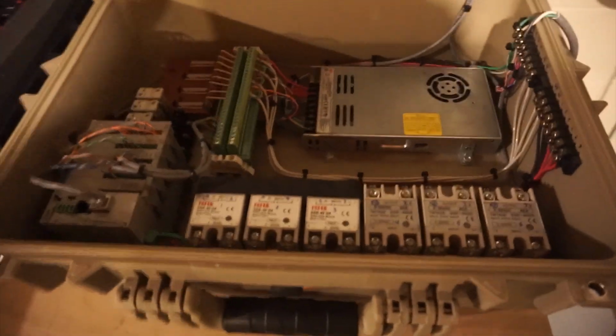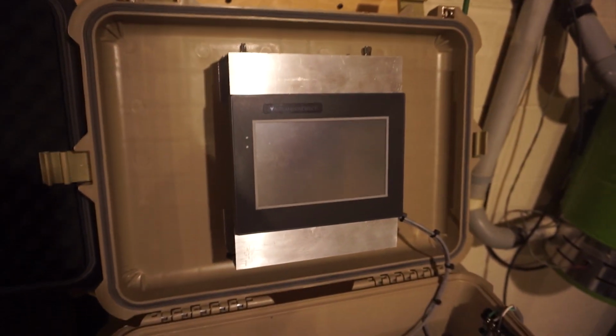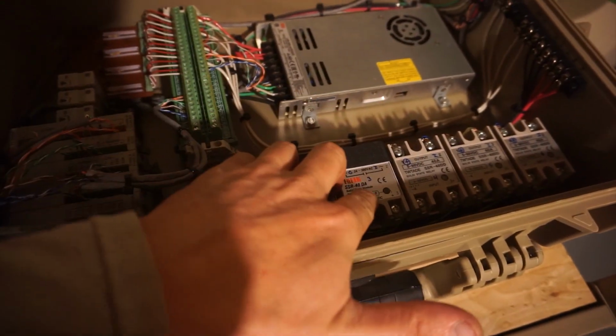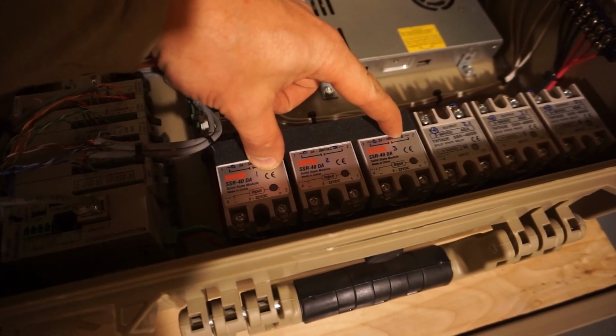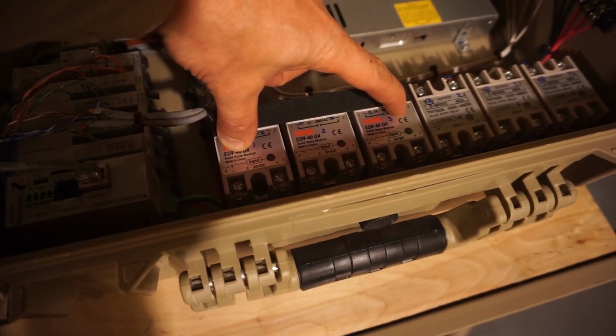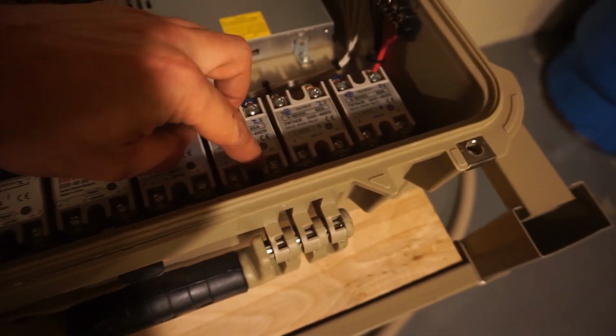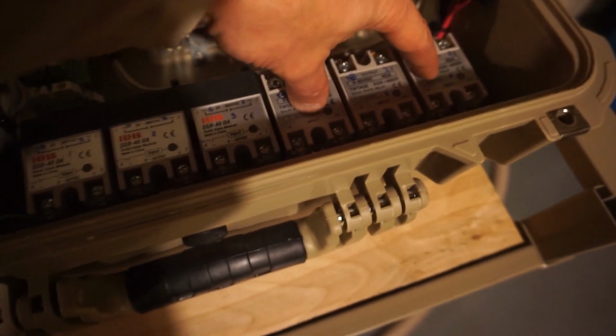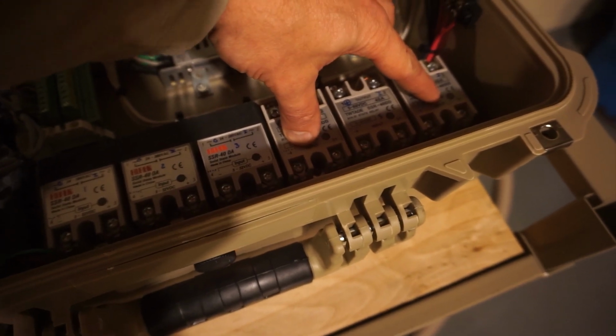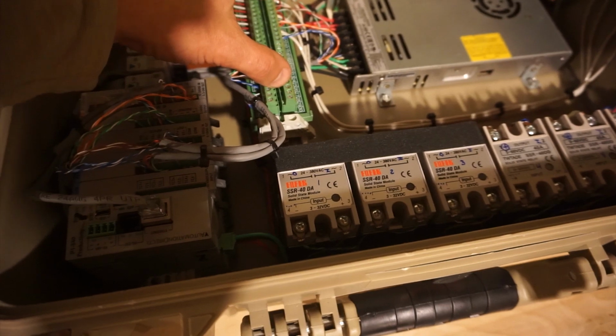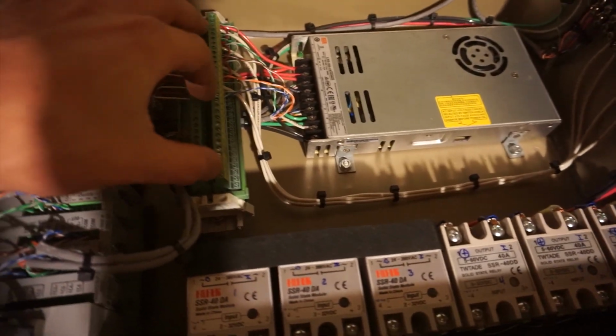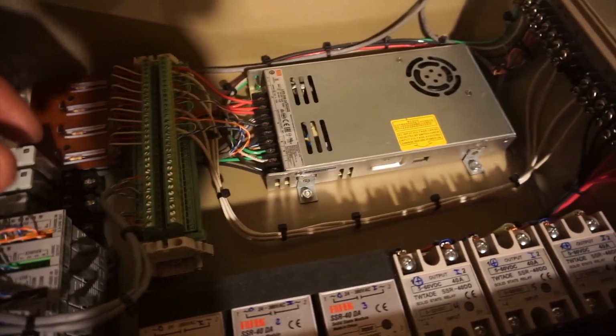So, this is the system that I use when I want to read what a transducer is doing, but I want to read it the way the control system is doing it. I wired this up so I could do 3 things. One is produce 3-phase outputs that could test a motor up to 40 amps. And then it has DC over here, and what these are for is for modulating, in my case anyway. I use them to modulate signals going into a VFD. This will also read high-speed inputs. It'll also read 0 to 10, 4 to 20, all the way down to 0. And this checks the capacity range of individual transducers on those 2 setups.